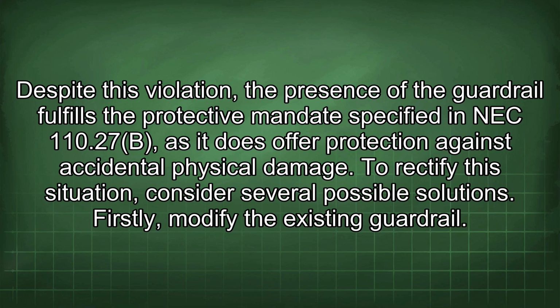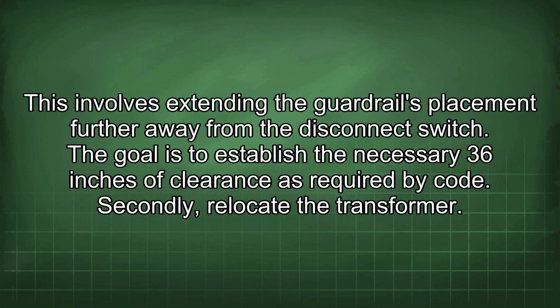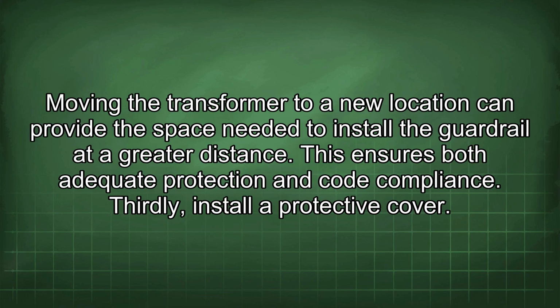Firstly, modify the existing guardrail. This involves extending the guardrail's placement further away from the disconnect switch. The goal is to establish the necessary 36 inches of clearance as required by code. Secondly, relocate the transformer. Moving the transformer to a new location can provide the space needed to install the guardrail at a greater distance. This ensures both adequate protection and code compliance.